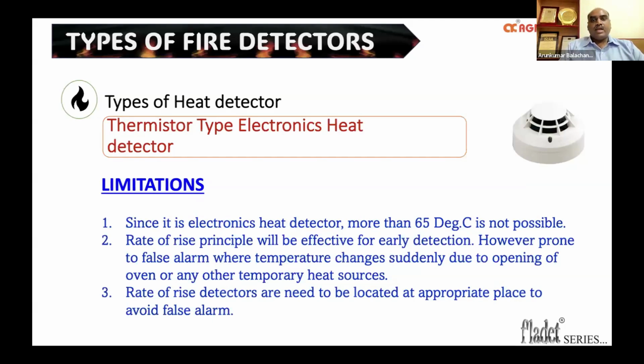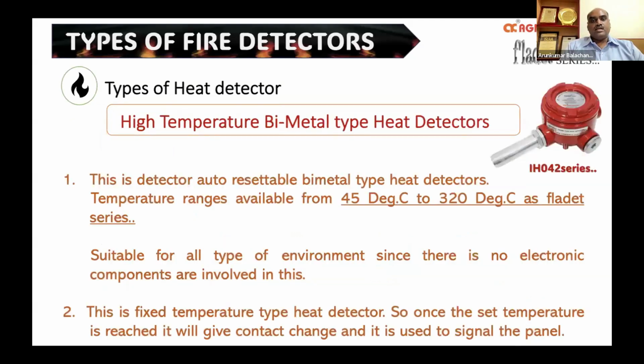We'll come to the mechanical type bimetal heat detectors. Unlike the electronic type, these mechanical type detectors can be set for a temperature between 45 and up to 320 degrees centigrade. And being a mechanical type detector, it can be easily employed in almost all environments, that is in a safe or a dusty place, or even in explosion-proof or flame-proof areas.